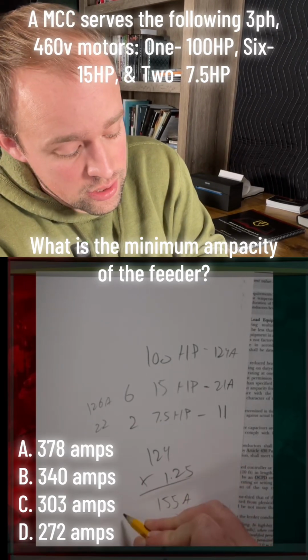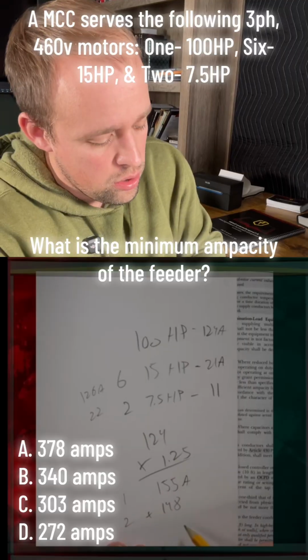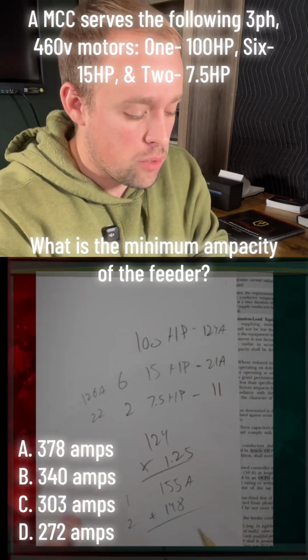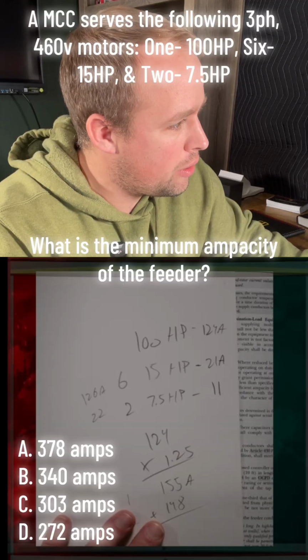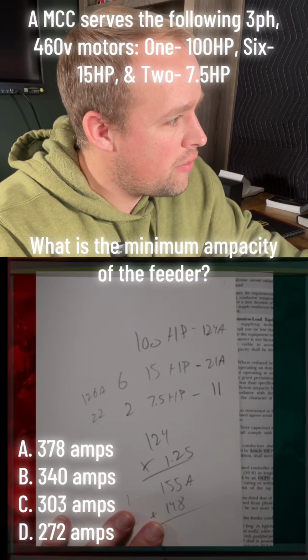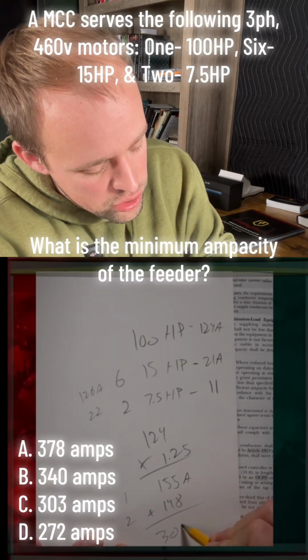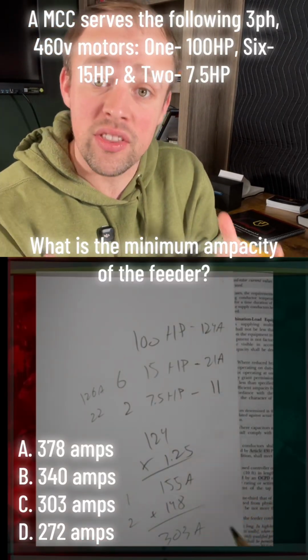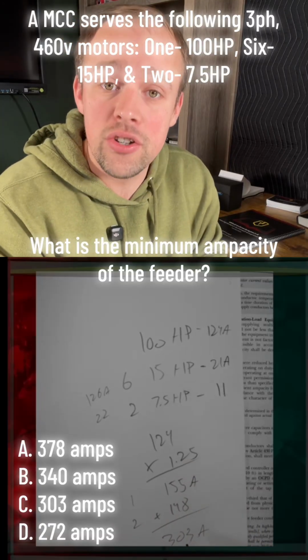So this complies with 1, this complies with 2, and now I need to add those together to be code compliant. So 148 plus 155 gives me an ampacity of 303 amps. So my conductors for this feeder have to be at least 303 amps.